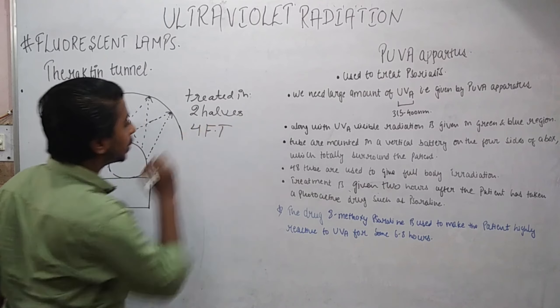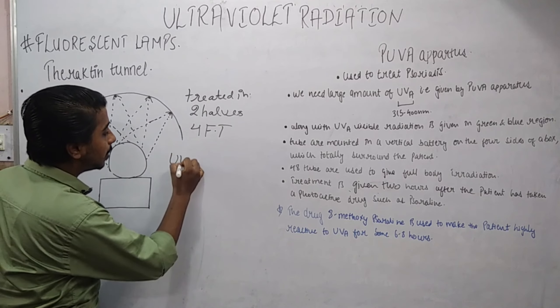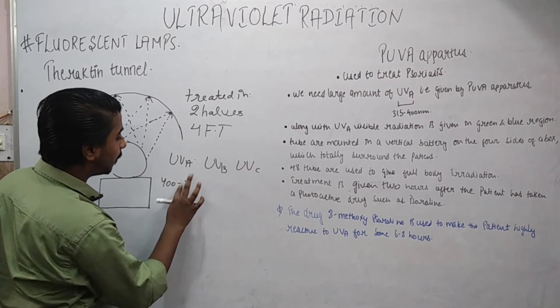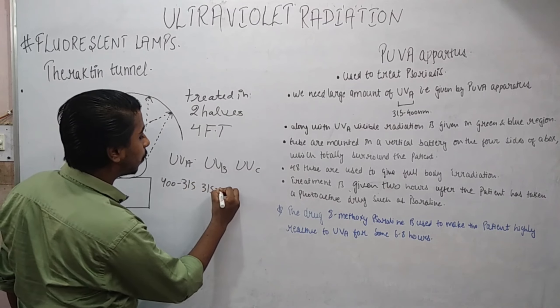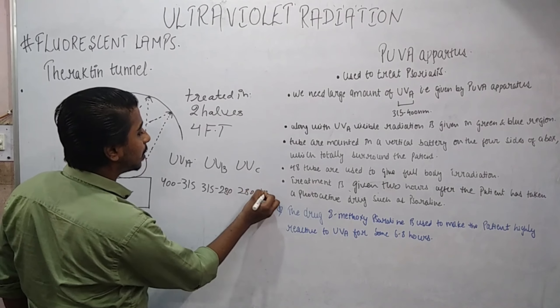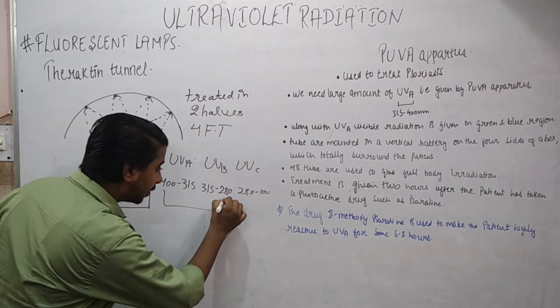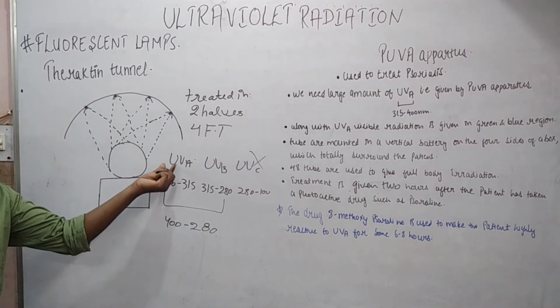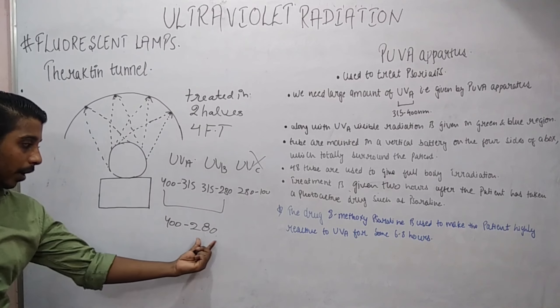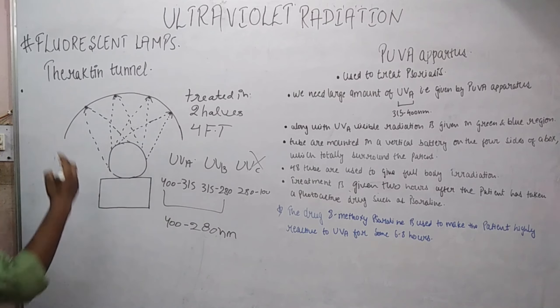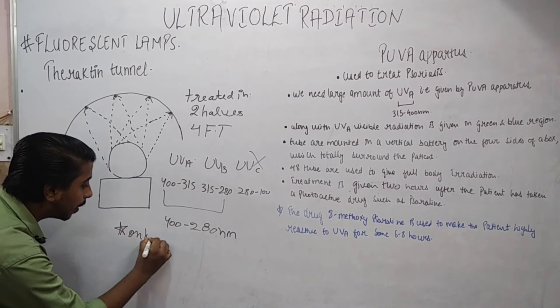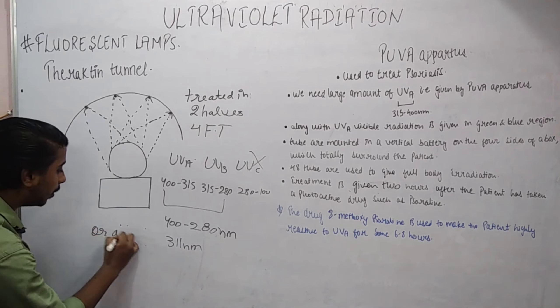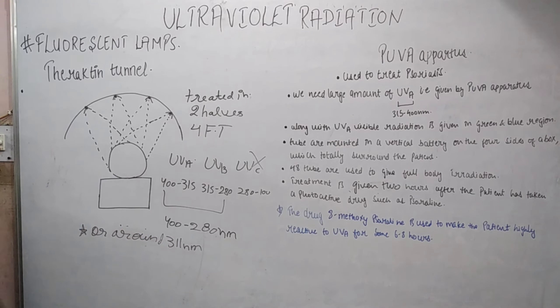There are a total of four fluorescent tubes. As we know, there is UVA (400 to 315 nanometers), UVB (315 to 280 nanometers), and UVC (280 to 100 nanometers). This theractin tunnel can give an output of 400 to 280 nanometers — that is UVA and UVB. There is also another type of theractin tunnel which gives an output of only around 311 nanometers.